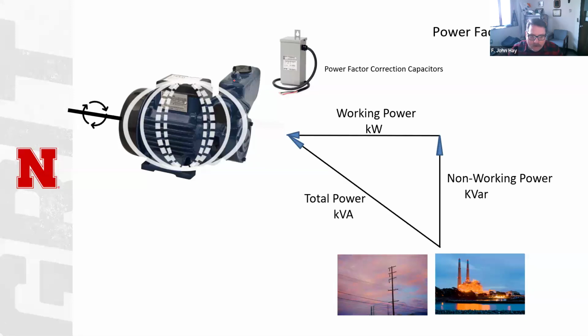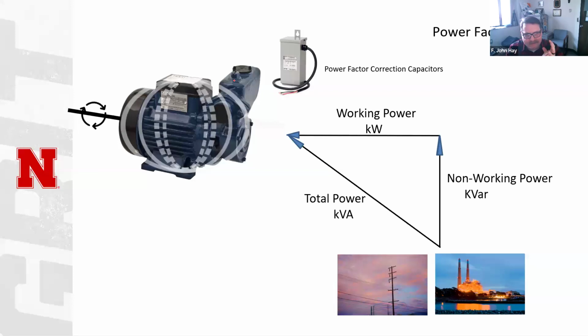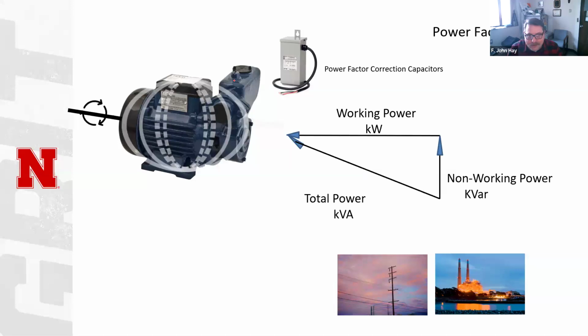So when we add power factor correction devices, these are simply boxes of capacitors. Capacitors are like batteries that aren't chemical. They actually store electric charges. And what that capacitor does is provide some of the reactive power to the system. Thus, when I have less reactive power or non-working power, I can reduce the total power, thus improving the power factor. And all I did was add a capacitor bank to the system. As long as that capacitor bank is functioning when the motor is functioning, I have a better power factor and can avoid some, and in many cases, all of those charges.